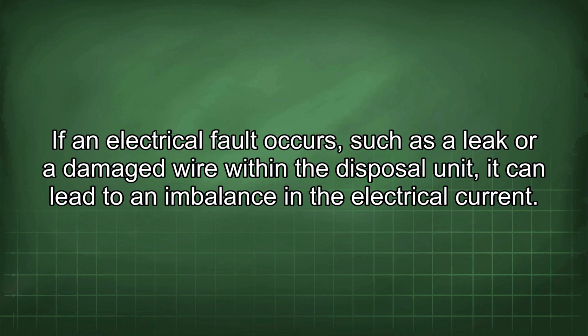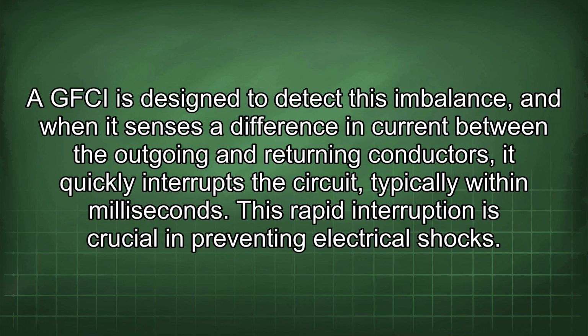If an electrical fault occurs, such as a leak or a damaged wire within the disposal unit, it can lead to an imbalance in the electrical current. A GFCI is designed to detect this imbalance, and when it senses a difference in current between the outgoing and returning conductors, it quickly interrupts the circuit, typically within milliseconds. This rapid interruption is crucial in preventing electrical shocks.